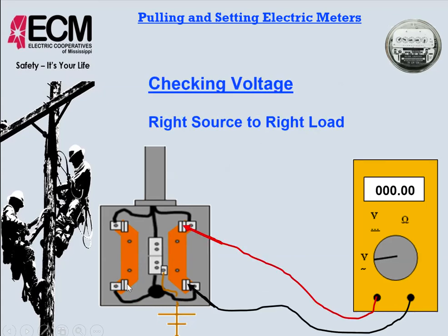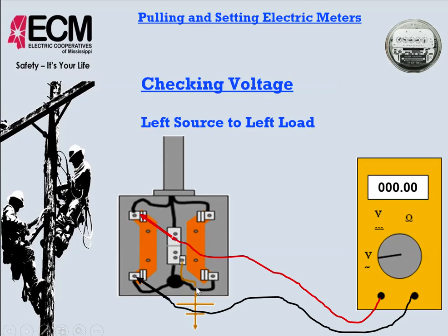Okay, the next thing we want to do is check the right side source to the load. What we're making sure of here is, we've already established that the potential difference between here and ground is 120 volts. So we want to check from line to load side to ensure that the load side is not grounded. If the load side was grounded here, we would have gotten 120 volts here. So making sure that the load side is not grounded, and we want to do that on the other side as well. Now there's an alternate way to check this as well.